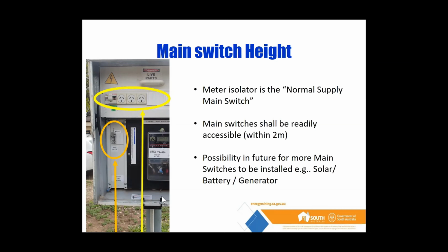We look at our top DIN, and there's no main switches there, so that's compliant. That's outside of the 2 meter exclusion zone. However, if we're to install a solar down the track, or a battery, or a generator, or any other source of supply, we're going to have to put a main switch somewhere. So generally it's going to be in that top DIN. And a lot of guys, when installing that, forget what they're installing is actually a main switch. So we have that problem, and we also have the problem of the guy who's installed the switchboard in the first place. So even if you don't do solar or batteries, when you are installing a switchboard, try and think about future works, and think about the poor solar installer that's going to try and figure out a place to put his main switch.